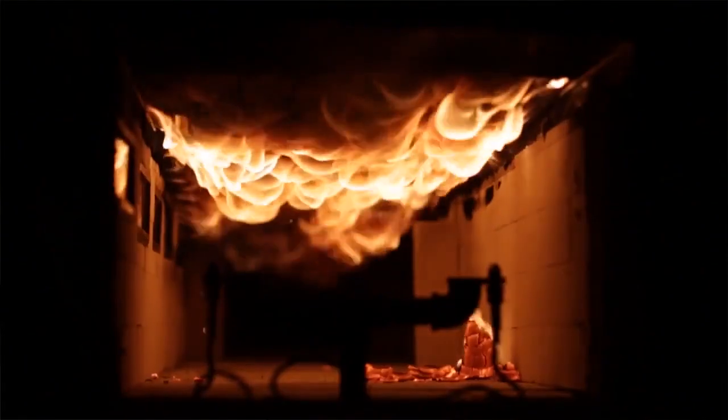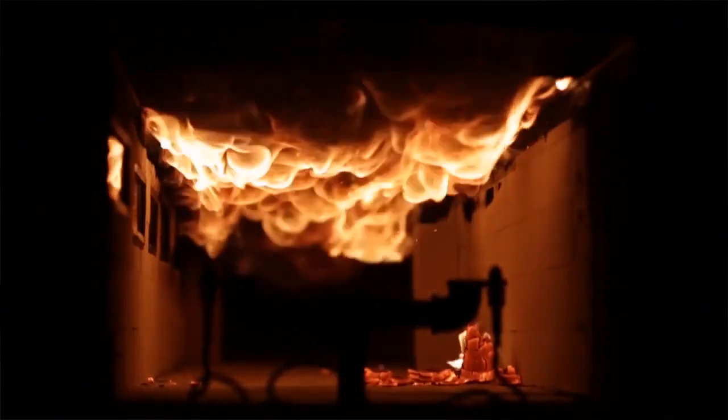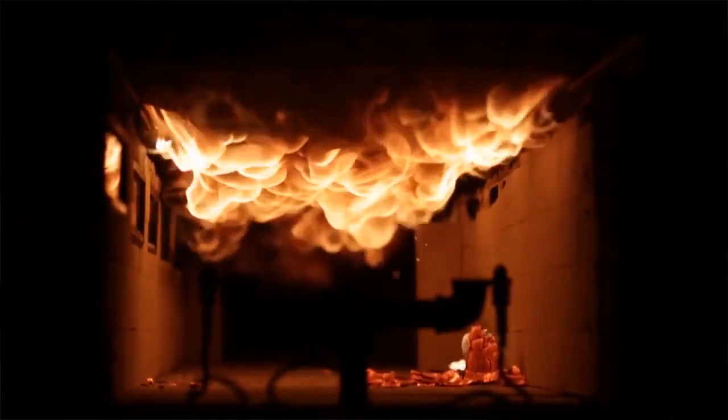Stone wool or mineral wool insulation typically has a flame spread rating of somewhere between 0 and 5. So what that represents in the test method is that the flame front doesn't advance much beyond 4.5 to 5 feet. In other words, not much beyond the igniting flame itself. That's not surprising because mineral wool and stone wool insulation are made from rock and slag, which is largely a non-combustible material. It does include a small amount of bonding agent, and that's where that little bit of flame spread or smoke develop comes from.